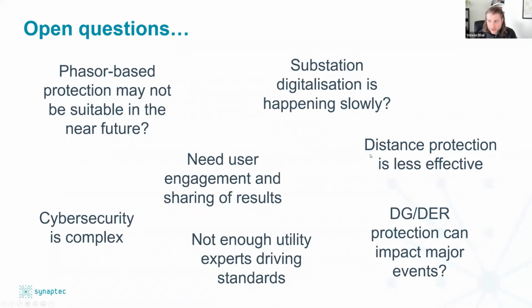As we've already mentioned, distance protection is becoming less effective as networks get more complex, and it has issues. It's very difficult to specify the settings and prove they are correct. It's much more complex than differential protection, and if differential protection is available, that is always going to be favorable.